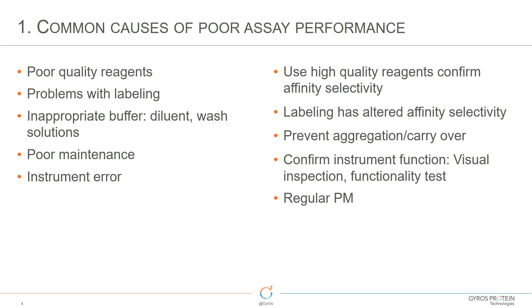We depend on the wash station cleaning the needles, and one of the common problems we see is if the wash station is not functioning properly, we're going to see carryover. Poor maintenance of the wash station and of the instrument in general is a real issue. Our instrument functions very well when maintained well. Following the user guide for daily and monthly maintenance — a clean machine generally works well. A few minutes every day will lead to strong instrument performance over the long haul, and this is common with all automated immunoassay platforms.